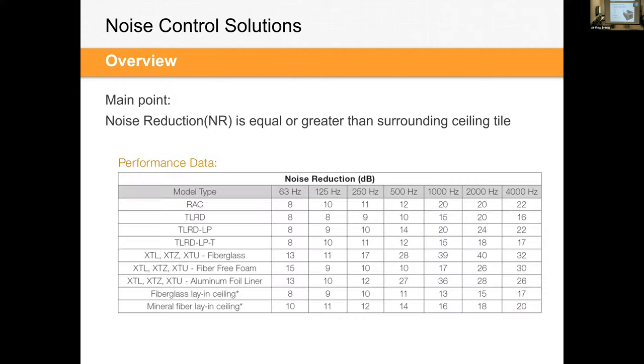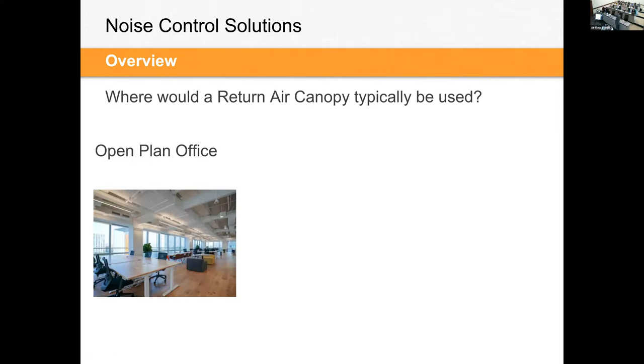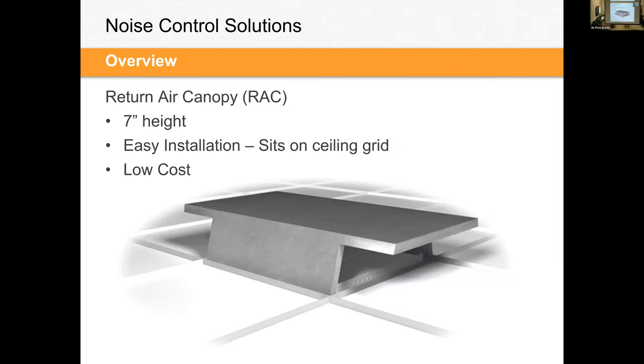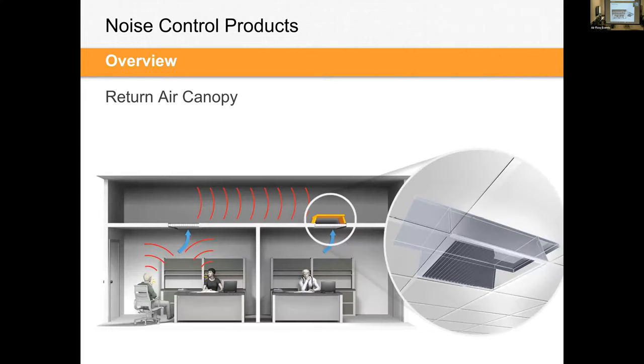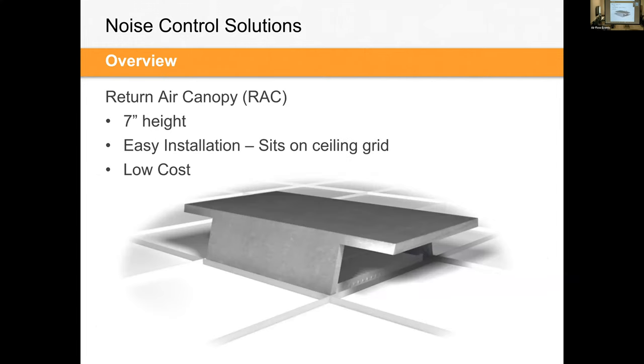Question real quick on the RAC. Is that acoustic media on the underneath side of that hood there? It is, yeah. If I go back a few slides, it's basically a sheet metal casing with fiberglass acoustic media underneath. Okay, and that media underneath, is that black in color? It's black, yeah. So it's the combination of the fiberglass and the sheet metal that gives you that transmission loss. And with these overhanging wings, we've developed it so it's an optimal size, and it works very well for that intention. The other thing that's nice is that these snap into the T-bar grid very easily.